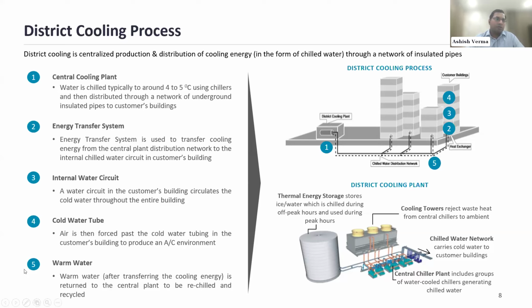I'll just use my pointer here. If you see on this image, this is the district cooling plant, which is sitting remotely from the buildings it is serving. These are multiple buildings catered by this single plant. This cooling plant generates chilled water at somewhere around 4 to 5 degrees C, which is then pumped to the respective buildings. In the buildings, there is a small piece of equipment called the ETS, Energy Transfer Station. It is nothing but a plate heat exchanger. On one side of the plate heat exchanger is the chilled water coming from the district cooling plant, and on the secondary side is the building-level chilled water system. Basically, we are segregating both chilled water circuits, building side and district cooling side, so that there is no mixing of the fluid.